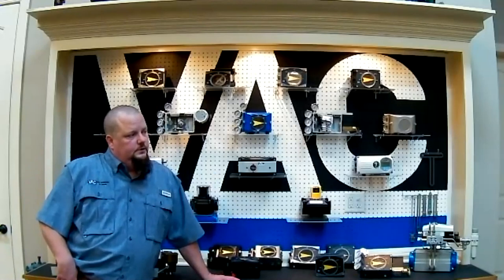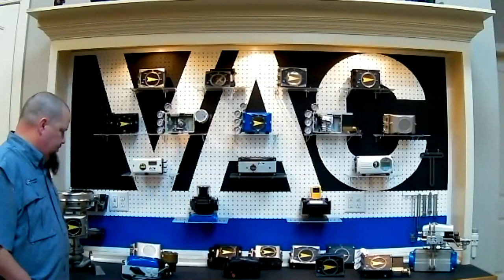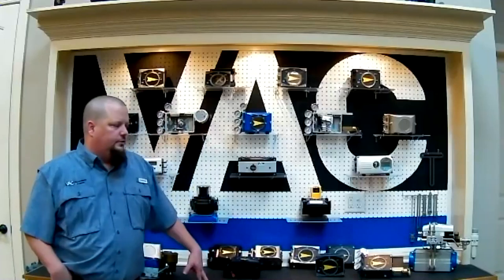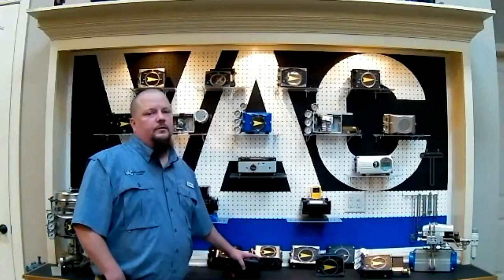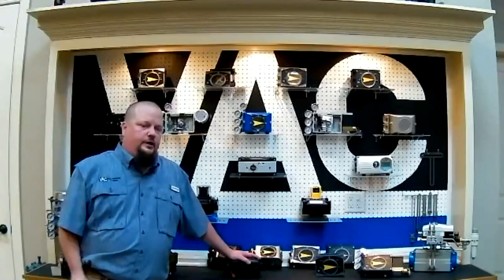All right. I think Carly has a question or two to ask here and see what everybody has to say. Question number 1. Is the extra high temp option available for electropneumatic positioners? David Cattleman, he's quick. He says no, and that is correct. Extra high temp and the low temp version are both pneumatic only. And you also would not be able to mount feedback in those units, for the same basic reasons: the 325 degrees on the extra high temp exceeds the limits of the electronic components inside.